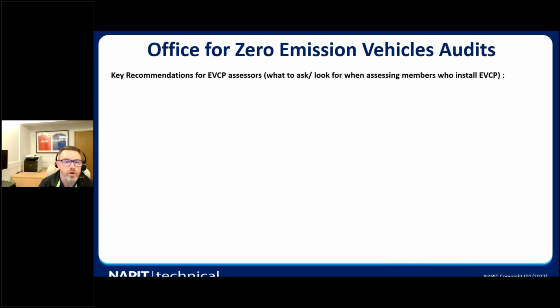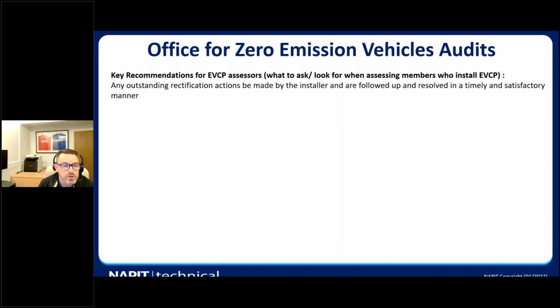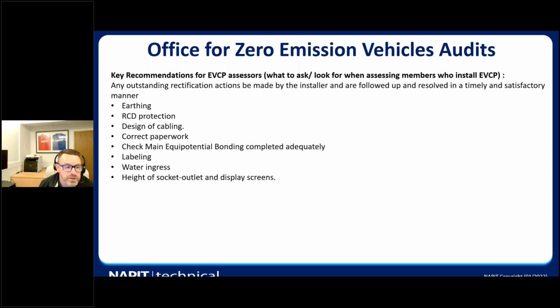The key recommendations for the assessors, which they were asked to look at when carrying out these audits, were that any outstanding rectifications made by the installer were followed up and resolved in a timely manner. It covered earthing, RCD protection, design of the cabling, the correct issuing of the paperwork for all aspects from certification to notification, and the DNO information as well. It also covered checking of the main equipotential bonding, labelling, any water ingress, the height of the socket outlets, and of the display screens of the EV charge points.